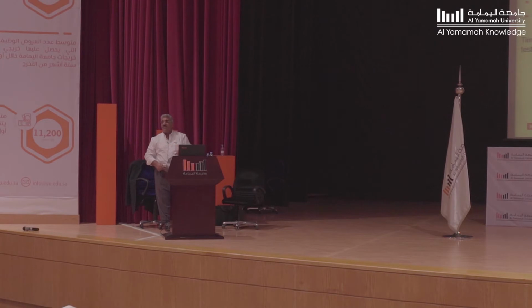That's why UL, as I said at the beginning of the lecture, is approved 100% in Saudi Arabia due to technical properties. So what do we do at Hilti, as experienced people with more than 35 years in fire stopping material? Before we send our material for approval to UL, we do internal testing. We have a furnace, and we will show you the test now in a video. After the test, we bring in the hose stream test. And if you see openings, light coming through, 1, 2, 3, this means that these 3 penetrations failed, and only these 2 passed. So if we didn't do the hose stream test, all the material would pass. The European would pass, but the Americans catch the failure.